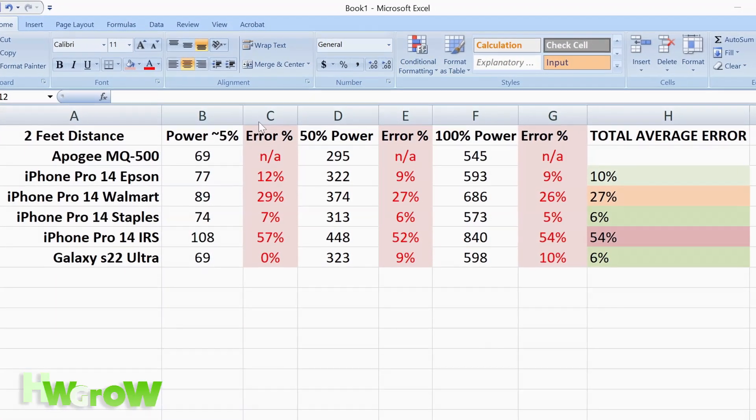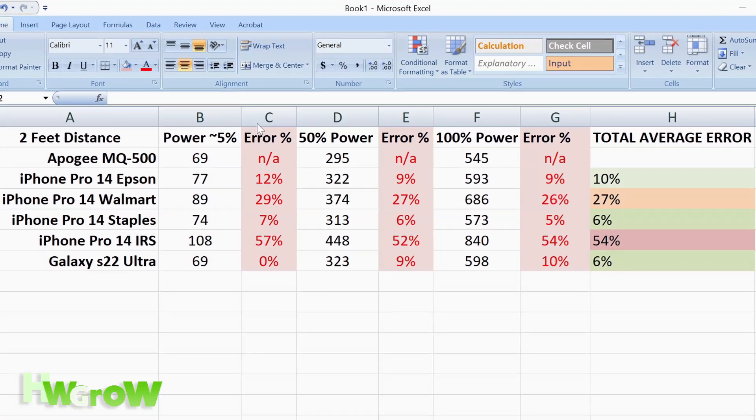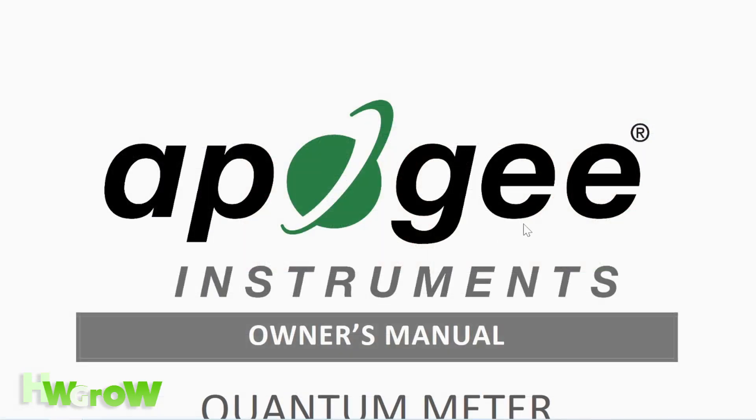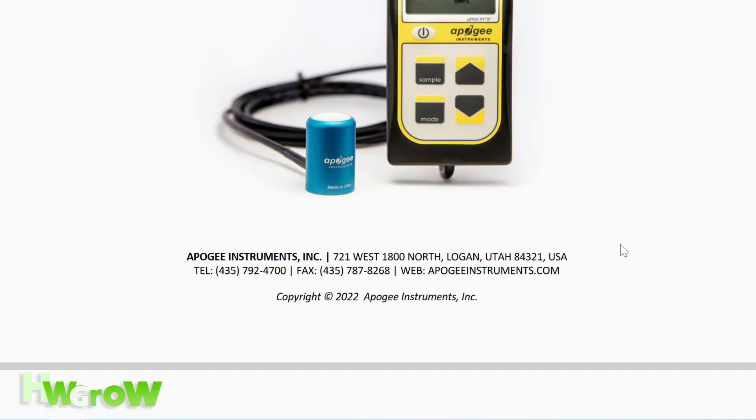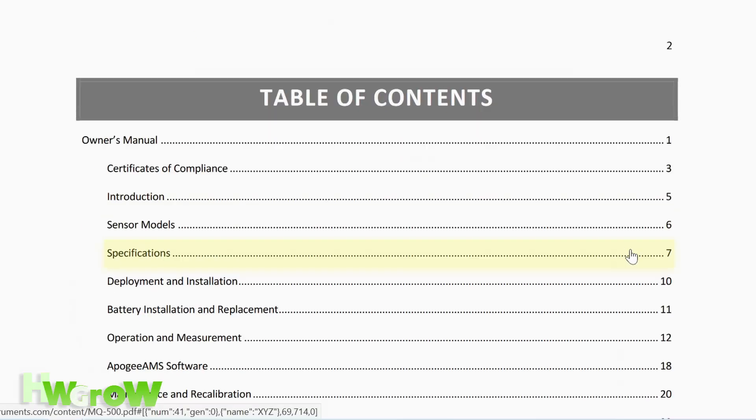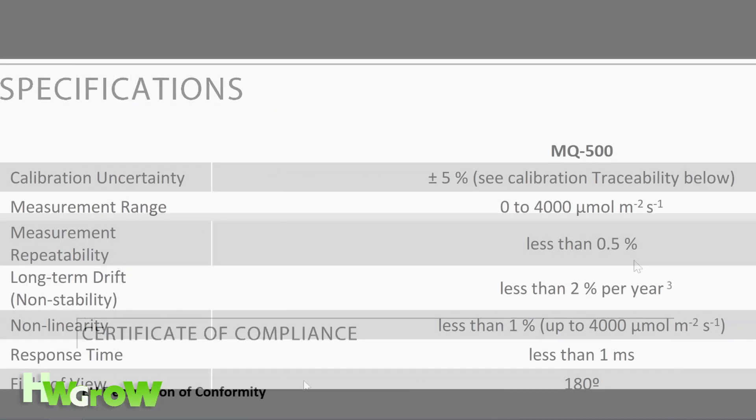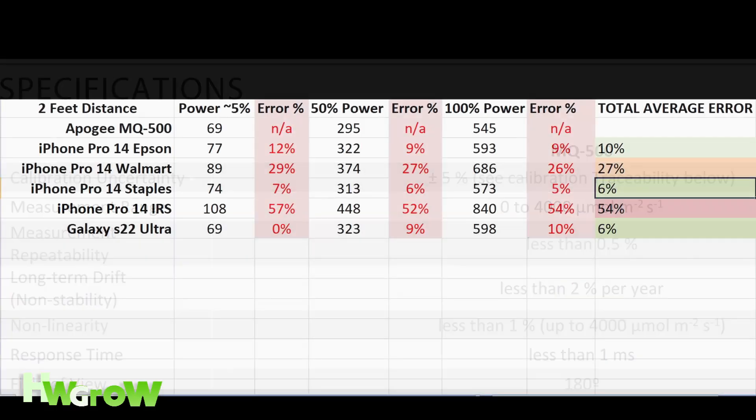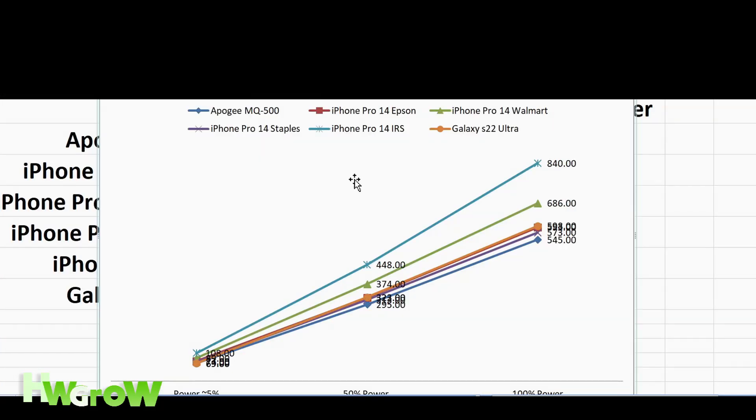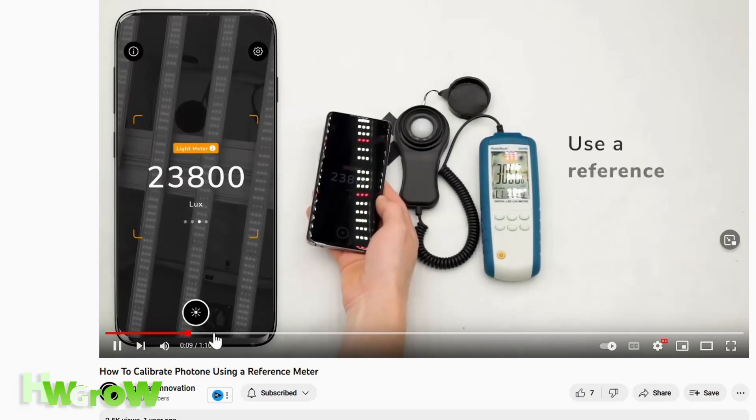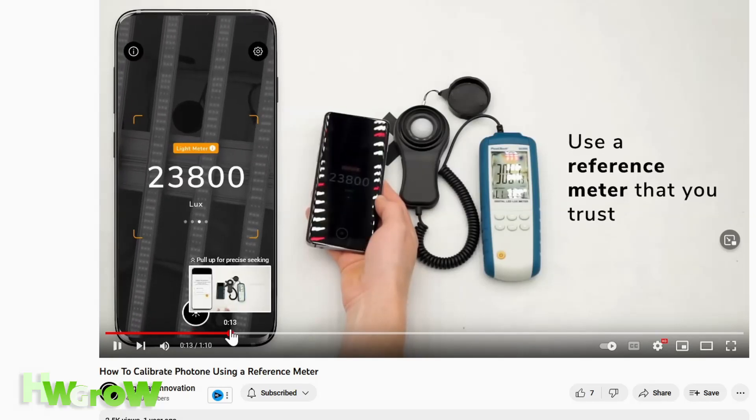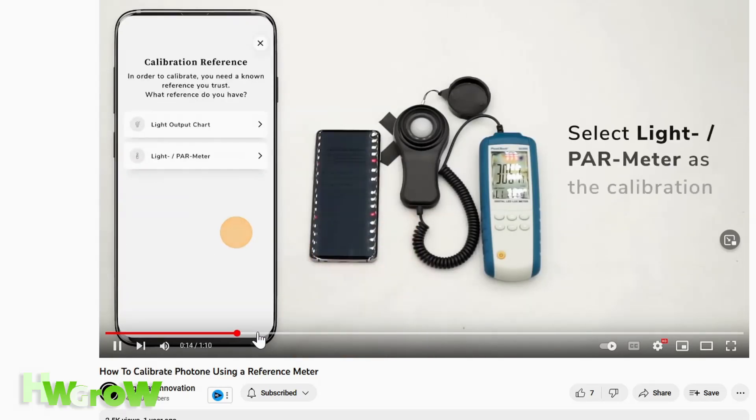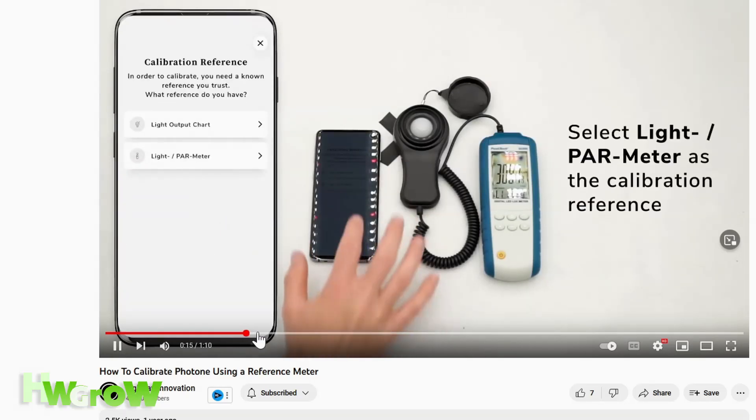So here it is, these are the results. It's worth mentioning that as stated on the manual, the Apogee may have a discrepancy of 5% straight out of the box. I had this data mapped out to a chart, and you could see it's linear, which is great because now you could calibrate it using the video linked in the description.